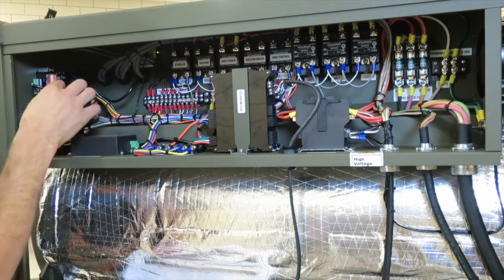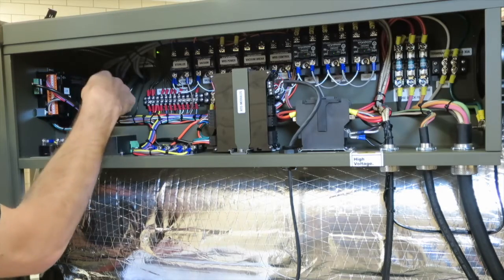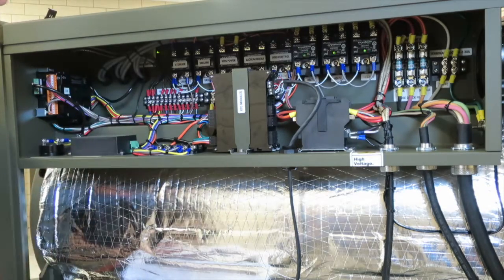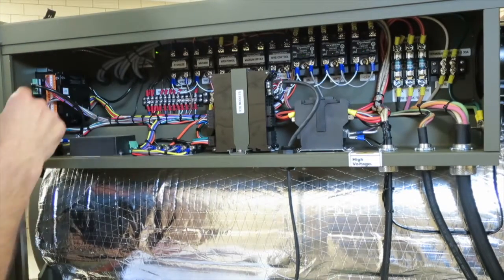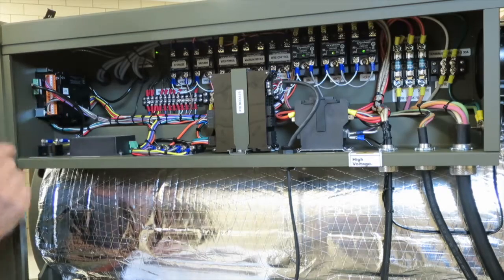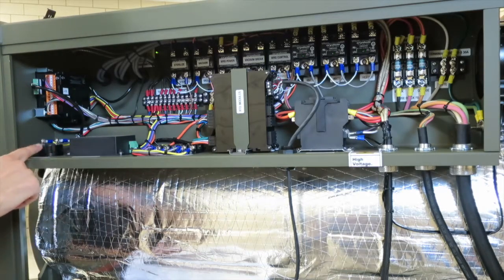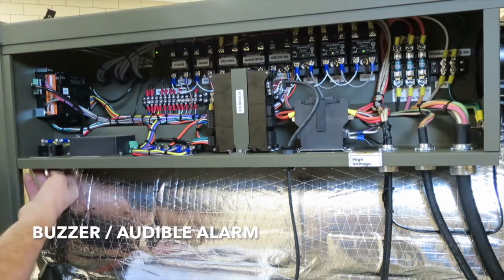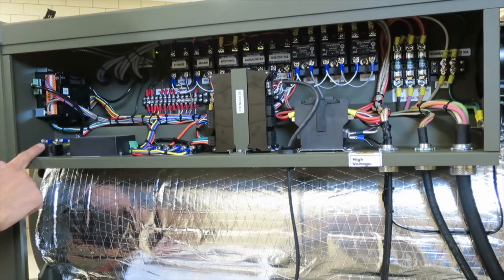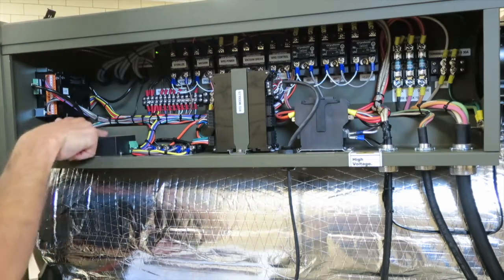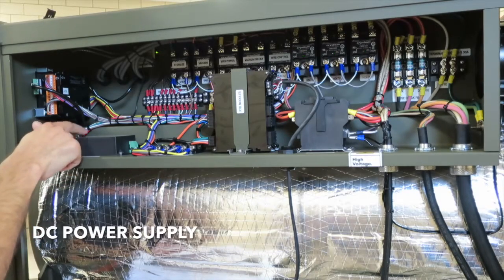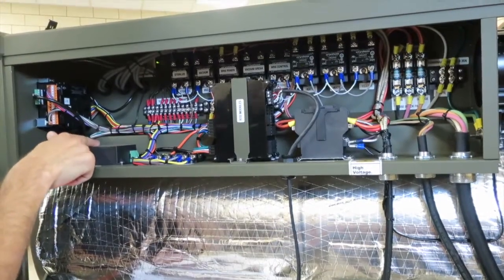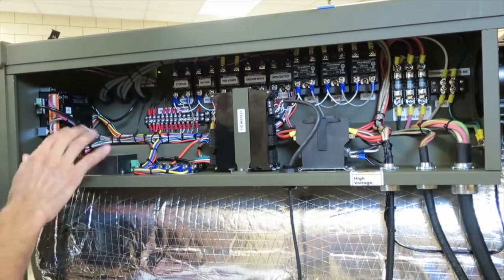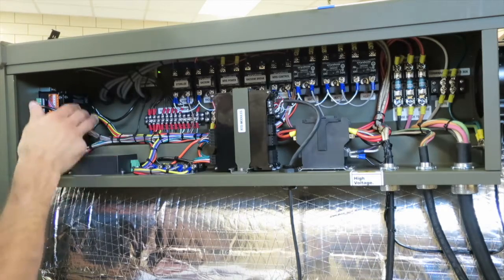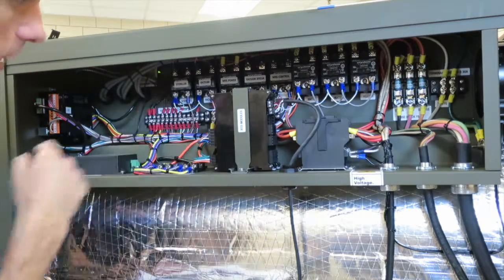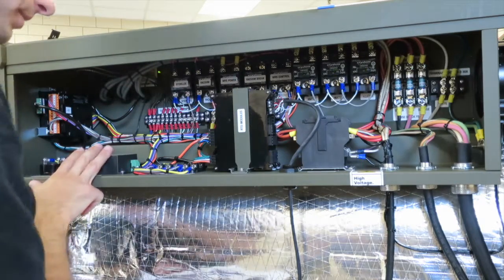You'll see that we have some input wires coming here. We also have some output wires coming here. And then we have the temperature coming in right here. So that's the PLC. Right here we have a buzzer alarm. Anytime you hear this unit beep, whether it's 1 time or 3 times, that's coming from the buzzer alarm right here at the bottom. Right here we have the DC power supply. On the left we have 120 volts coming in, and on the right we have 24 volts coming out. This power supply is what supplies power to the PLC, to the transmitters. Anything that needs 24 volts is coming from this power supply.